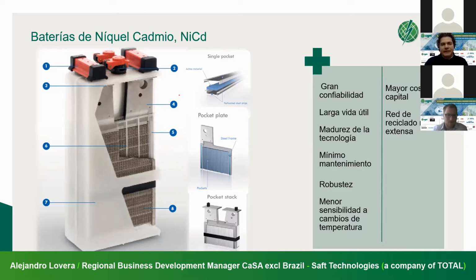For instance, working at 40 Celsius degrees, I can still get more than 70% of its normal capacity. The problem of nickel cadmium is the investment cost, the capex, although the lifespan of the battery makes the total cost of ownership lower. This is a higher investment. In fact, if we only see the initial investment and not the full history of the cost of the solution over a long time, it tends to have a disadvantage compared to the more traditional lead acid batteries.